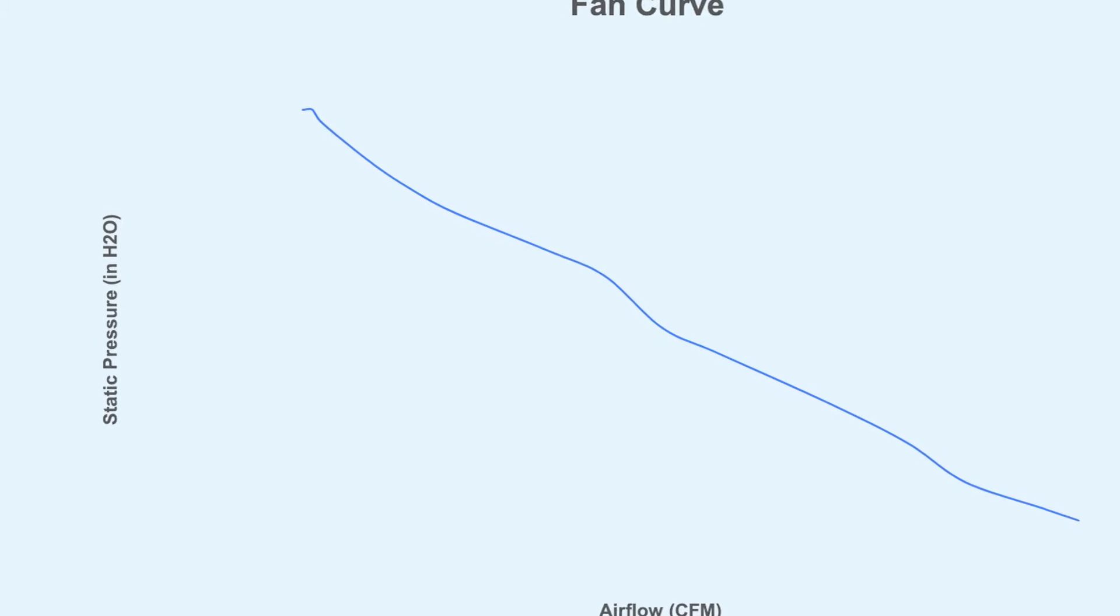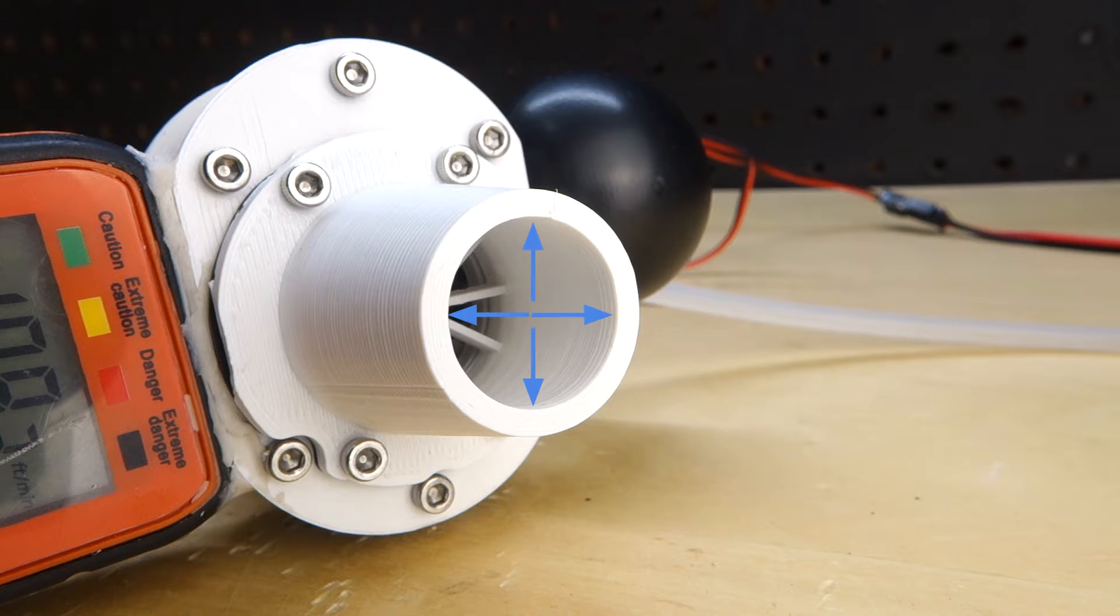Now that we visualize the airflow measured in CFM, let's look at the y-axis, which is the static pressure measured in inches of water. Now what happens is when the fan will blow air, the airflow will exert pressure on the walls of the adapter. And that is called static pressure.